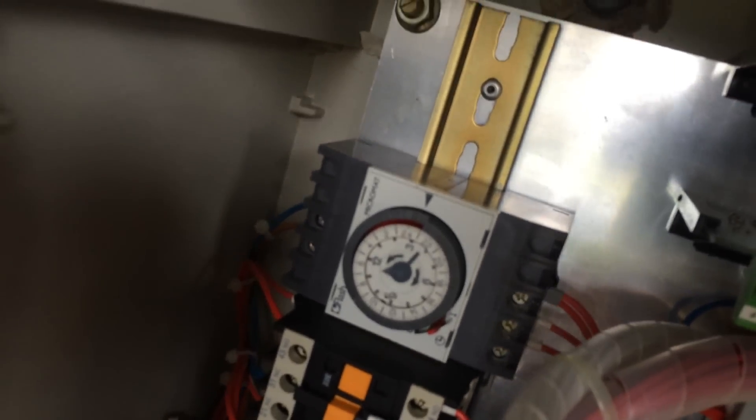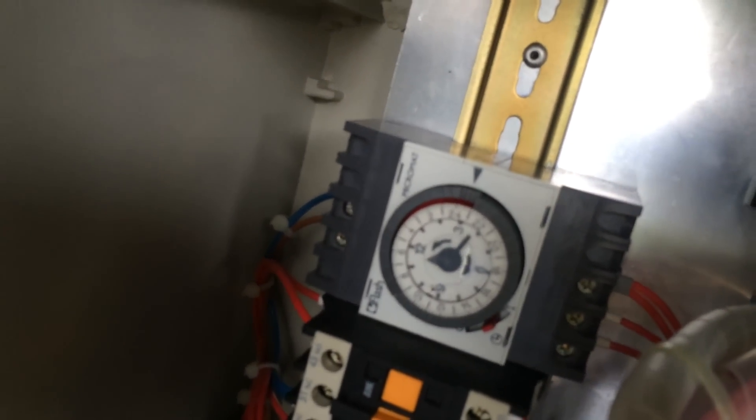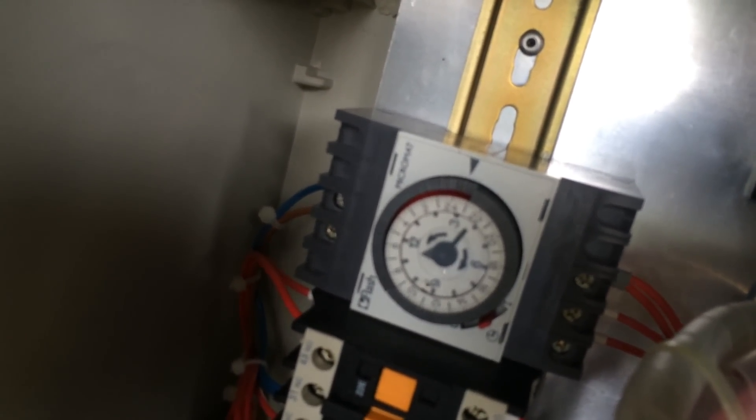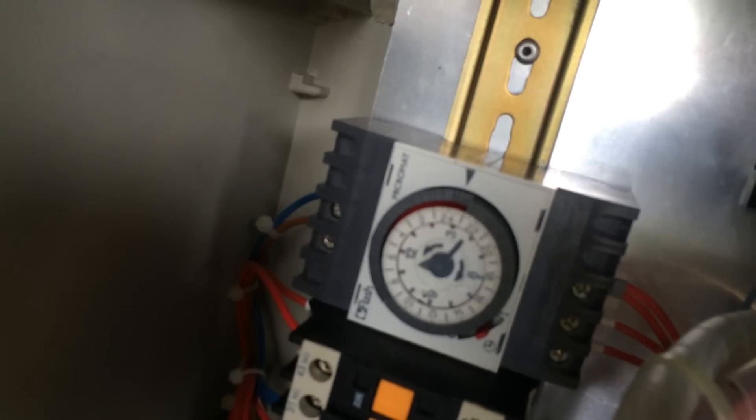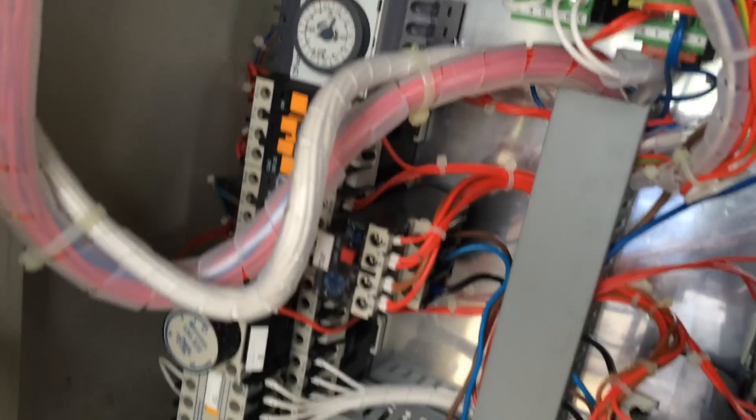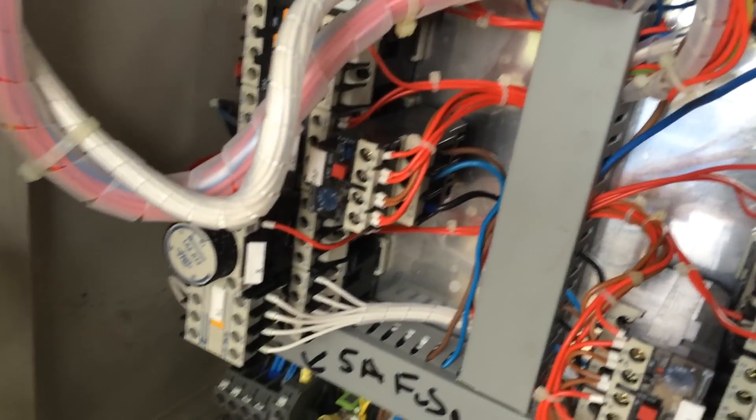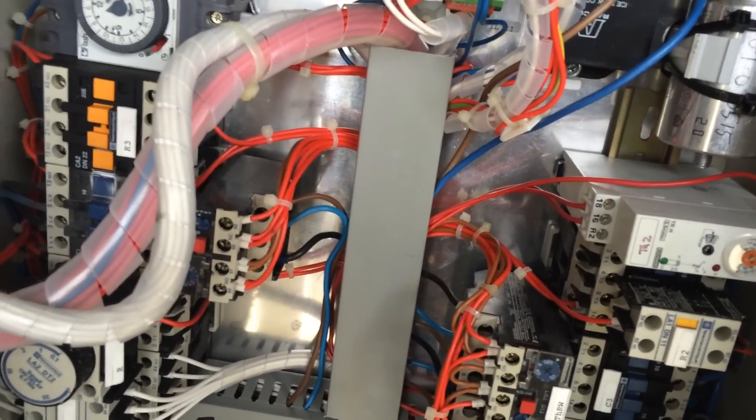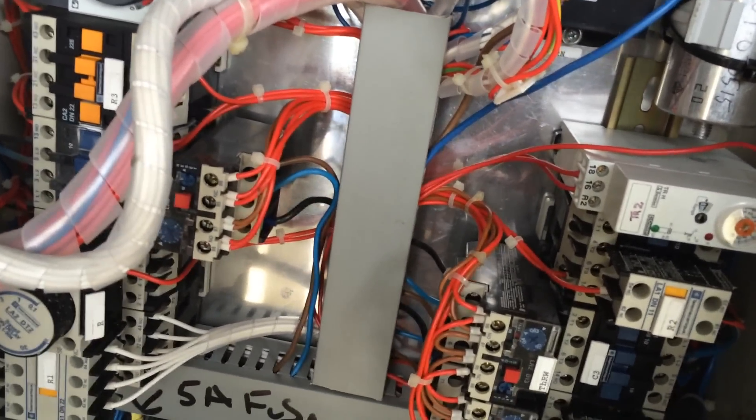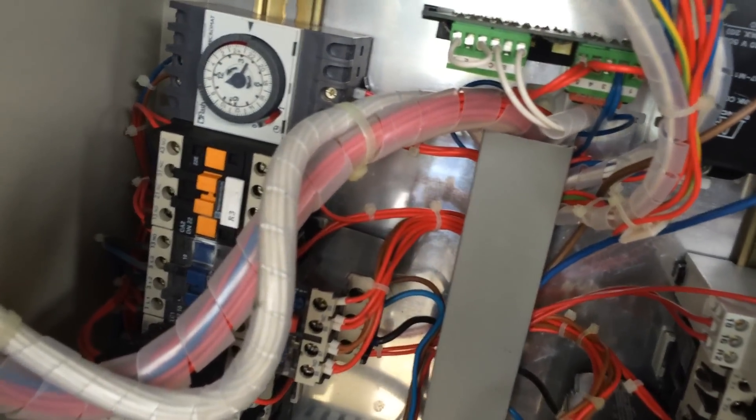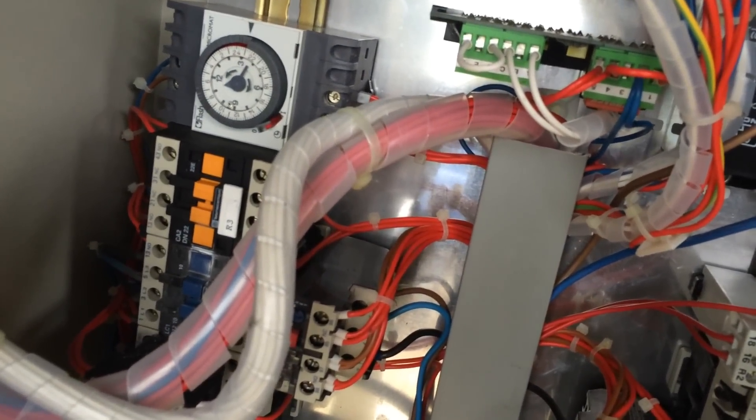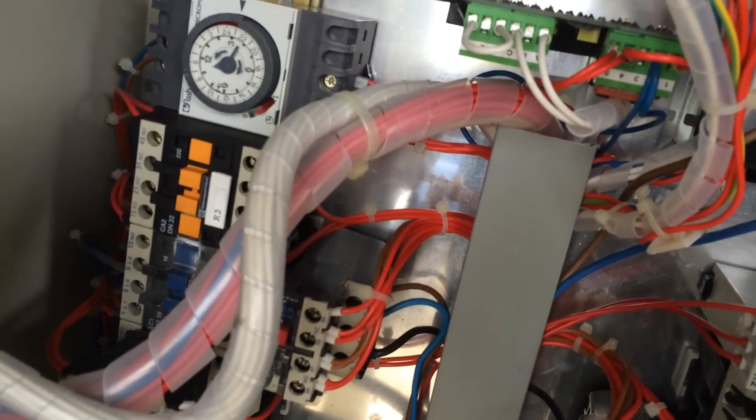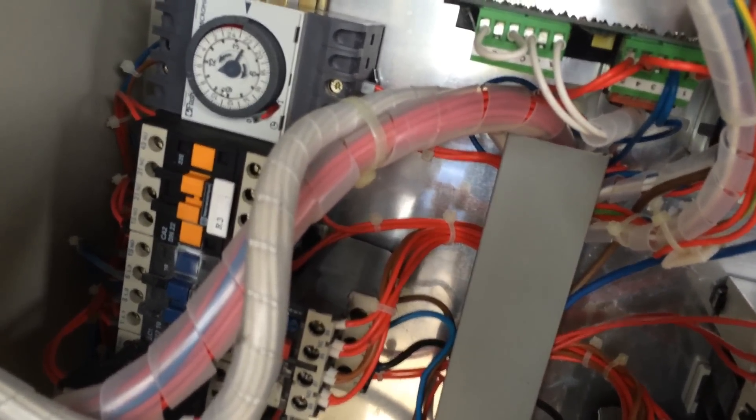So then we started thinking maybe the clock is faulty. I've had the counter going now for probably 10 to 15 minutes, and the clock hasn't moved at all, so it's probably starting and stopping. Probably the other days it's been in the off section, and the tank's been cooling just on the low ice probe, which will cool but it's just very slow because you don't have any ice reserves. It's got to cool it at the time.